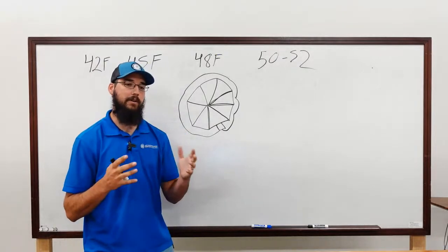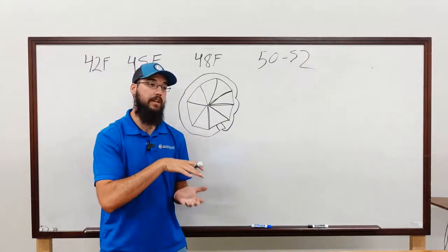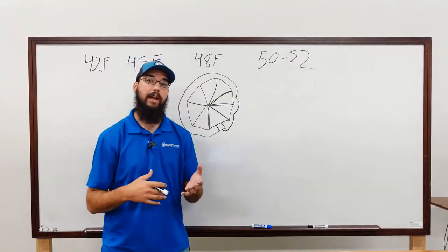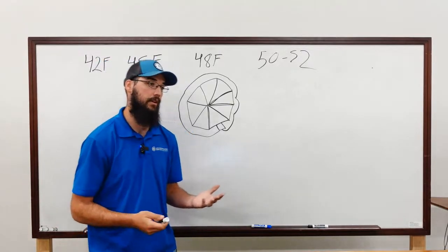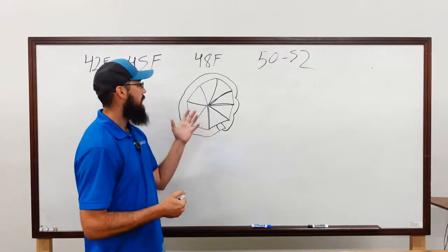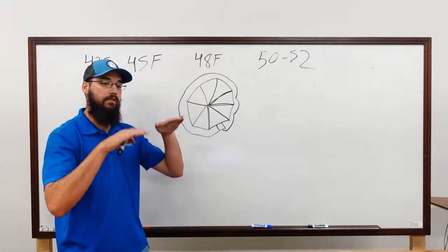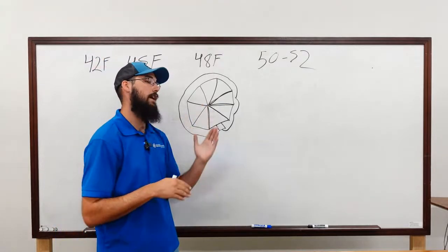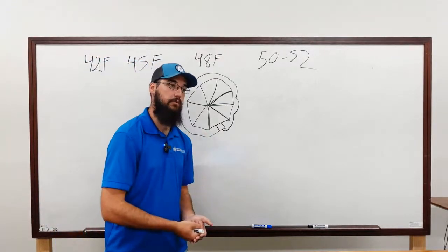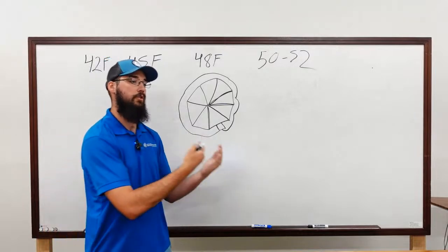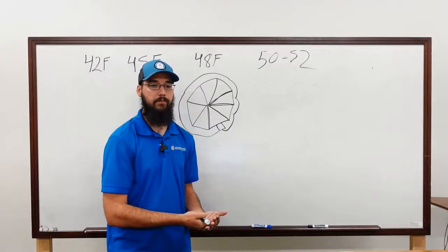Well, we're not talking oil, we're talking refrigerant. But yes, that impeller is then able to spin up and get up to speed. And that chiller will run at that state for several seconds to a couple of minutes, depending on your parameters. And it does that so that everything can stabilize, the motor can get to the RPM it wants to, and everything can start to level out on the machine. And then your guide vanes will start to slowly crack and creep open. The more they open, the more refrigerant you move, the more BTUs you move, the more you're going to cool that water down. And it's pretty well as simple as that.